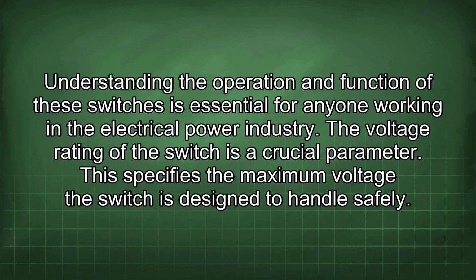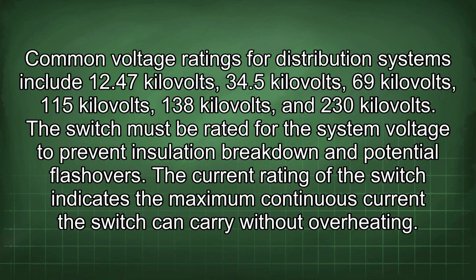The voltage rating of the switch is a crucial parameter. This specifies the maximum voltage the switch is designed to handle safely. Common voltage ratings for distribution systems include 12.47 kV, 34.5 kV, 69 kV, 115 kV, 138 kV, and 230 kV. The switch must be rated for the system voltage to prevent insulation breakdown and potential flashovers.